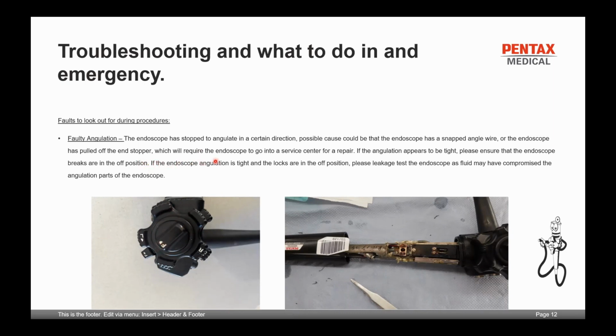If the endoscope angulation is still tight and the locks are in the off position, please perform a leakage test on the endoscope, as fluid may have compromised the angulation parts of the endoscope. So if you have a look here, this is where all your angulation components are connected together, through your segment stay coil wires, you have angle wires. And as you can see, all the corrosion and the buildup would definitely hamper the angulation of the endoscope. In this situation, it probably would have made the angulation very tight, to the point that it probably might have snapped.